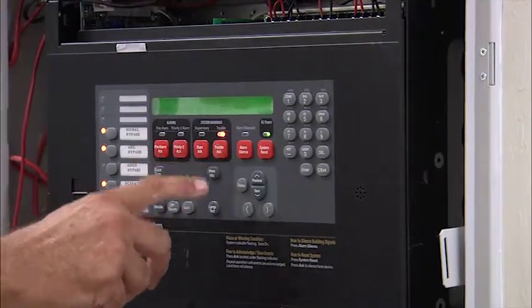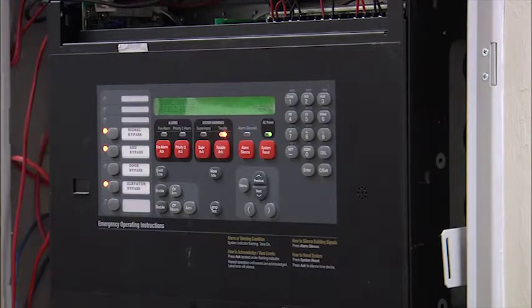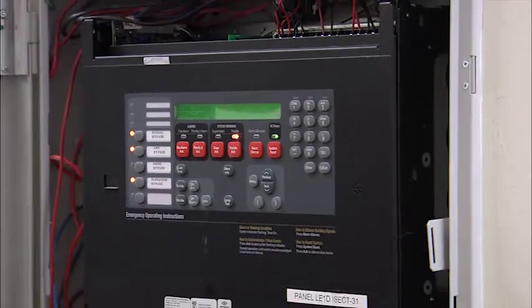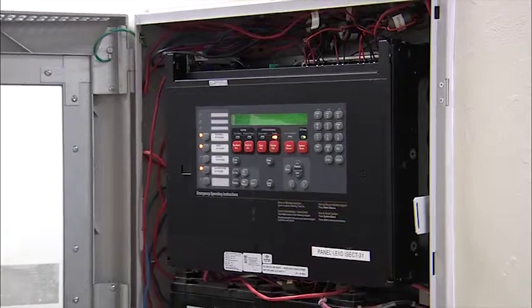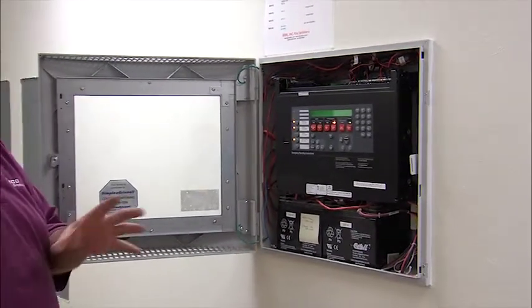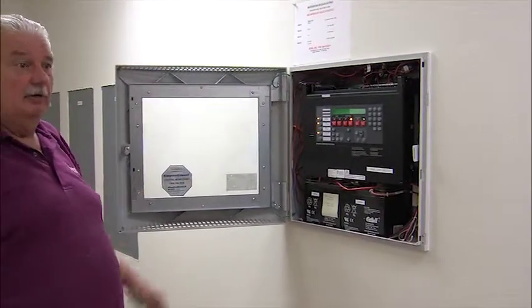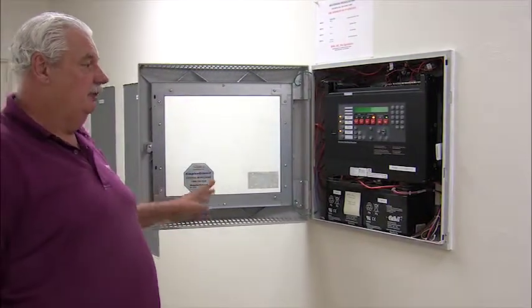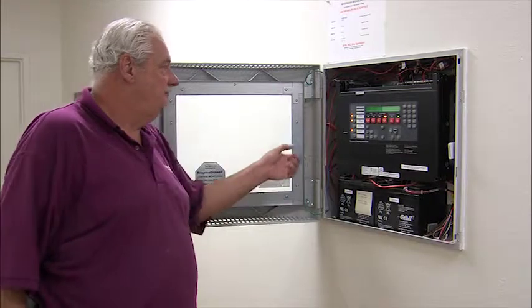Like I said, we do not recommend you use the signal bypass unless you know somebody's in the building working on your sprinkler system, or on your suppression systems for your control UPS room. This way, if they trigger something, it doesn't activate and evacuate the whole building. And just make sure before you do that, you call and put the system on test.